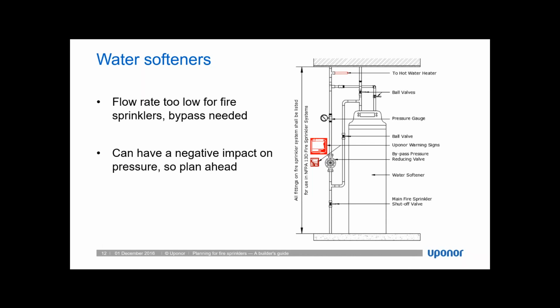If you see here, I'm showing a typical sprinkler riser. We tee off and we go into the water softener. We come back out of the water softener and we tee back into our main sprinkler riser. In between those two tees, you can see a pressure-reducing valve and a pressure gauge.